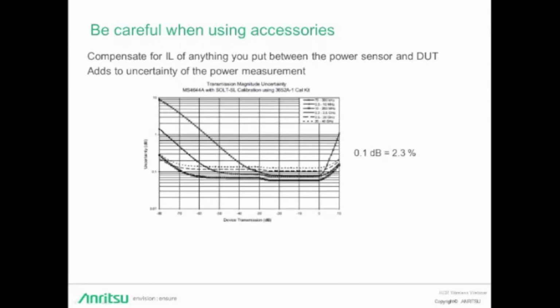So as a final note, you want to be careful when using seemingly benign accessories between your sensor and your DUT. For accurate measurements, you'll have to measure the insertion loss of anything you put in between the sensor and the DUT and back it out of the measurement. The insertion loss will have its own uncertainty, adding to the overall power measurement uncertainty.